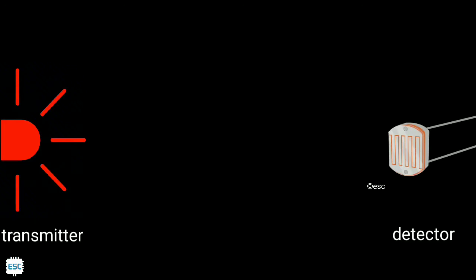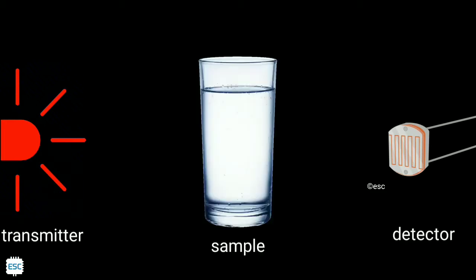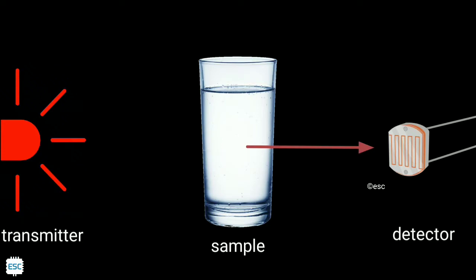Now let's see the working principle of a turbidity sensor. A turbidity sensor has two parts: one transmitter and one receiver or detector. Transmitter simply transmits the visible light or any kind of light and detector detects that light. When we place a sample in between transmitter and detector, the transmitter light passes through the liquid and the intensity changes. The change in intensity of the light is directly proportional to the turbidity. If the liquid is more turbid, the intensity is very low. So we can simply measure turbidity by measuring the intensity at the receiver. We can use photodiode or LDR to detect the light intensity.